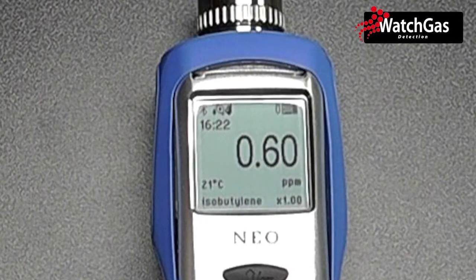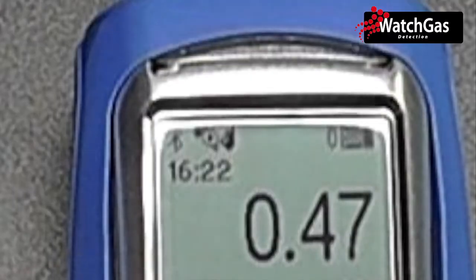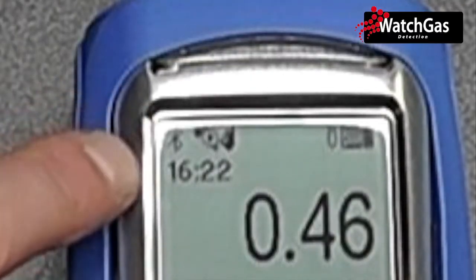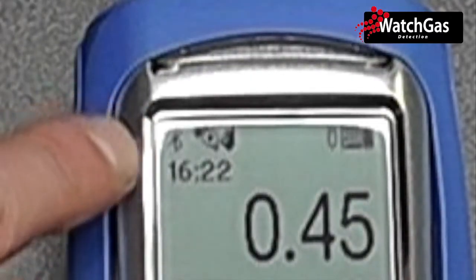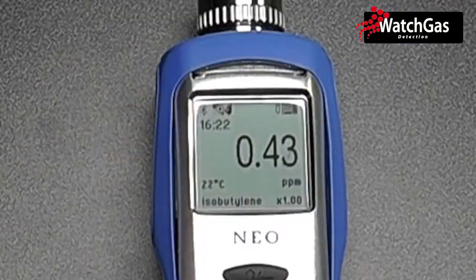So as we can see, the unit has started up and we're getting a reading of 0.57 ppm. So this gives us an extra layer of sensitivity against a standard photoionisation detector, and we can see we have the Bluetooth symbol to let us know that we are able to connect to a phone via Bluetooth, that the pump's operational, that everything's okay.